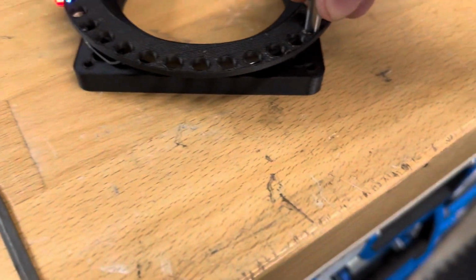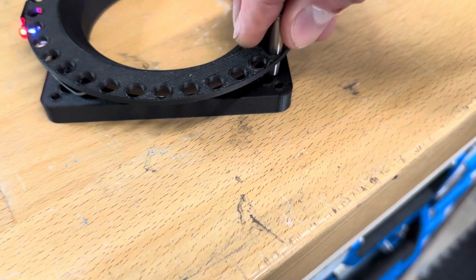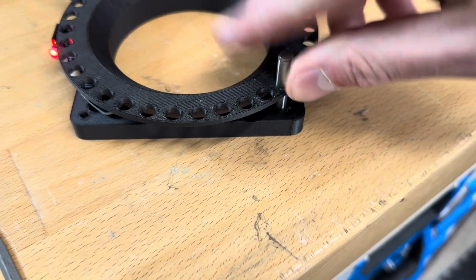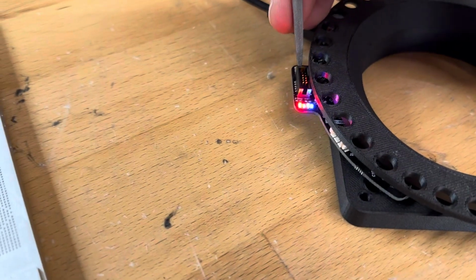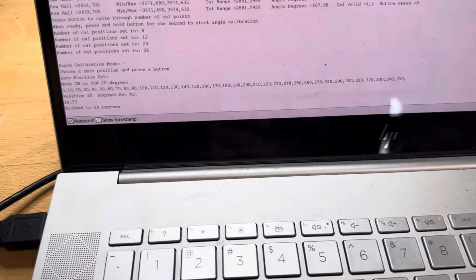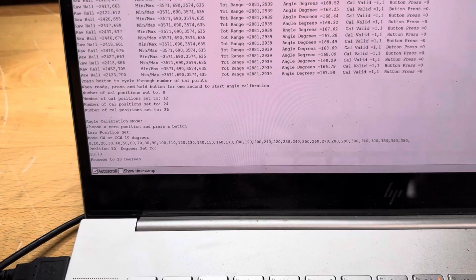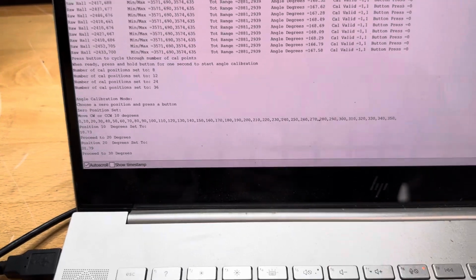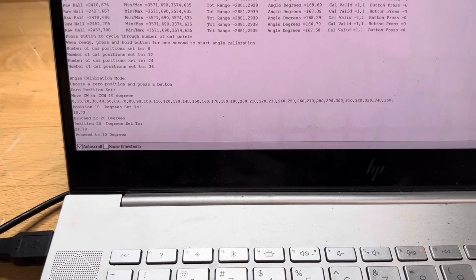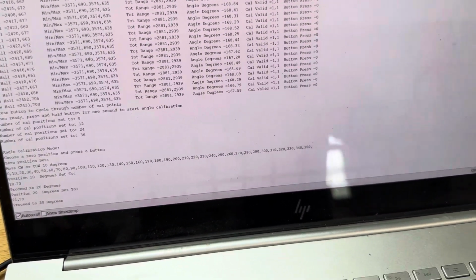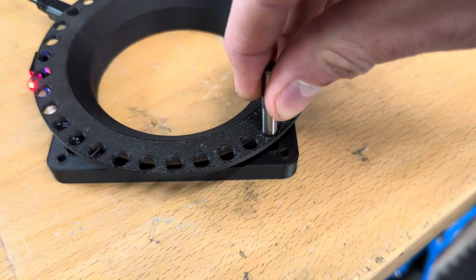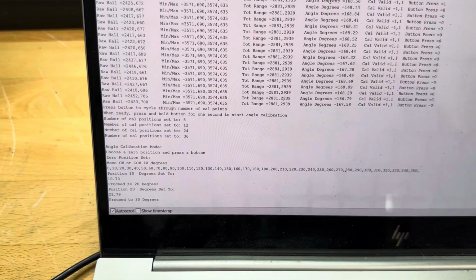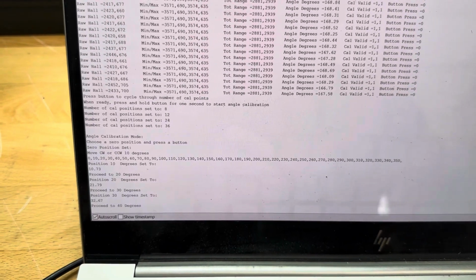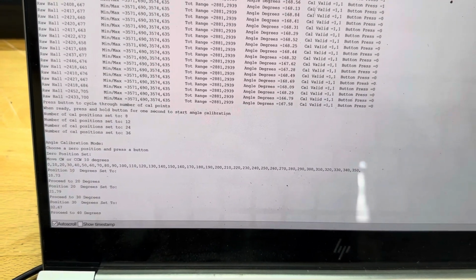And I'll do a couple of these. I'm not gonna do them all. So now I'll go to 20 degrees. I'll put that in the 20 degree spot, push the button, and you'll see that when I press the button, it's now recorded the 20 degree position as 21.79. So the sensor thinks actual 20 degrees is 21.79, and that will linearize it. Now I'll go to the 30 degree, and we're not gonna go through all these, obviously. And I'll press the calibration button. Oops, so it recorded 30 as 32.67. So you can see right there, we got a couple degrees off already.